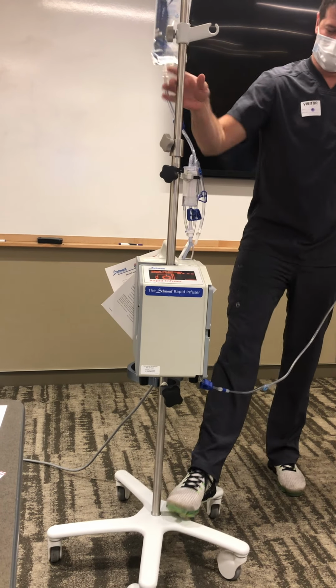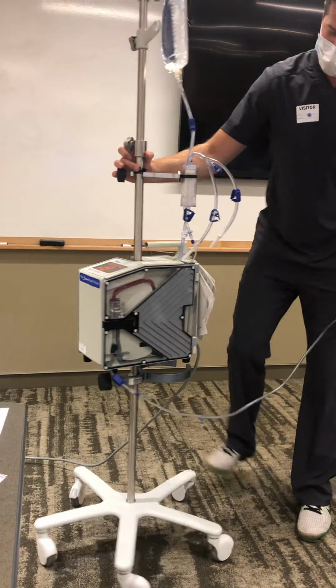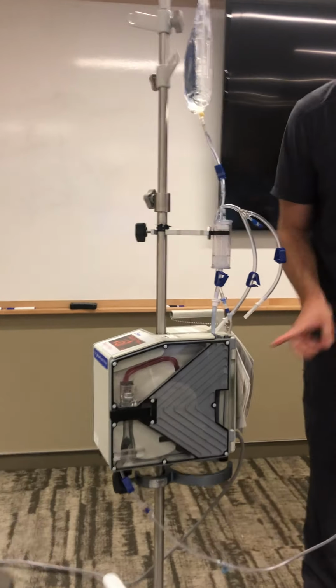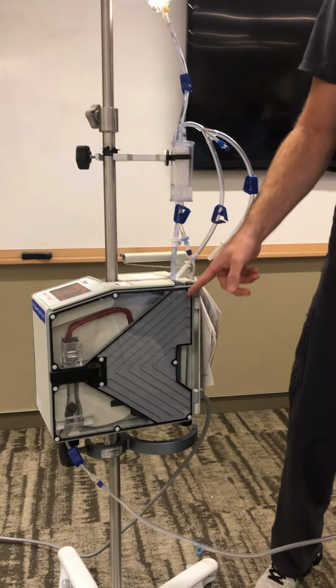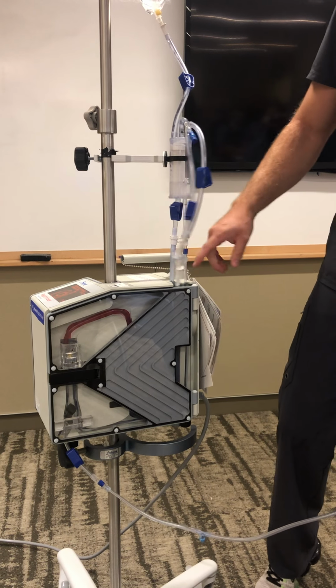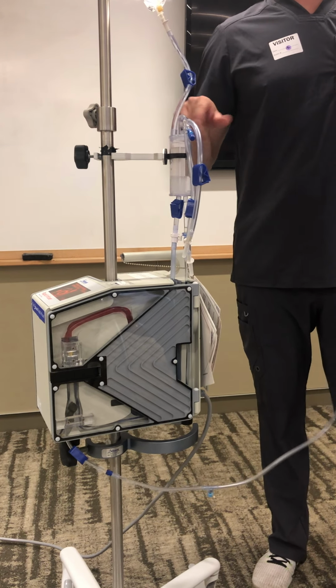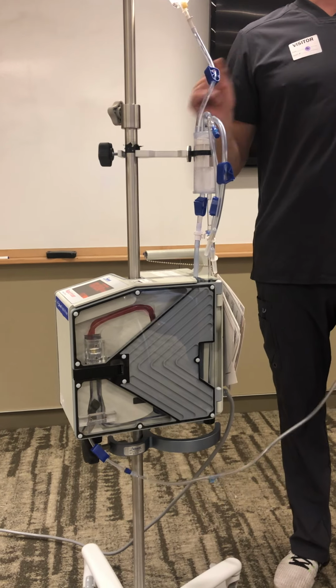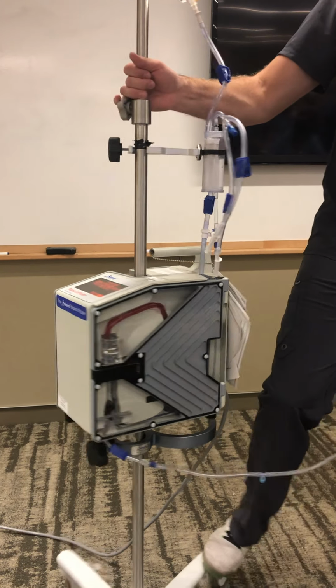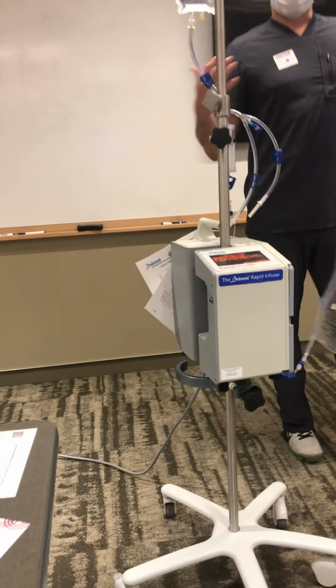There you go. What's happening is there's a countdown from 100 right here. We're flushing 100 mLs of fluid through this system, forcing the air out through this recirculating line and through this vent, so it's priming itself. I think that's what you were alluding to, right? Yeah, in a matter of 12 seconds, it has primed itself.